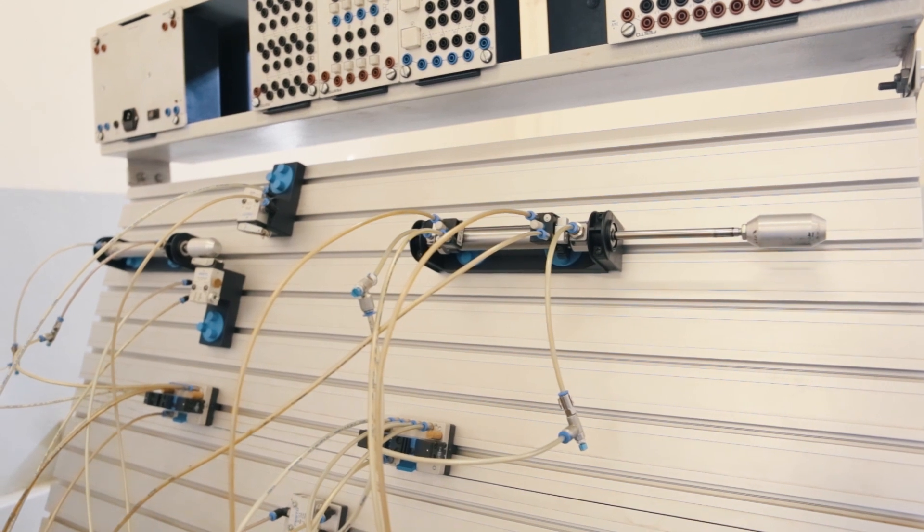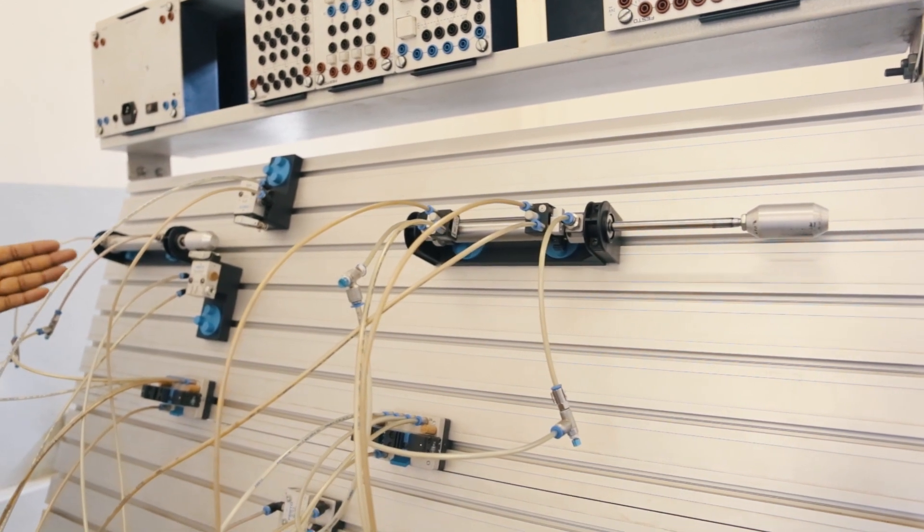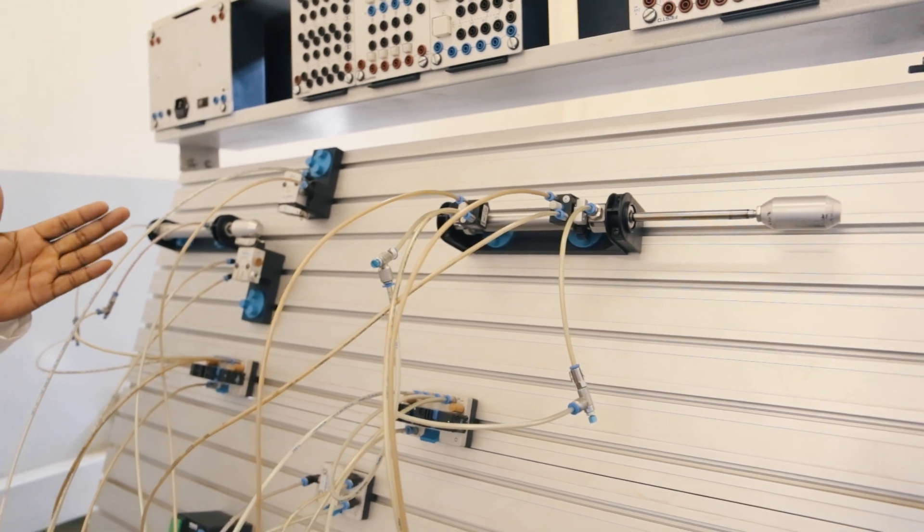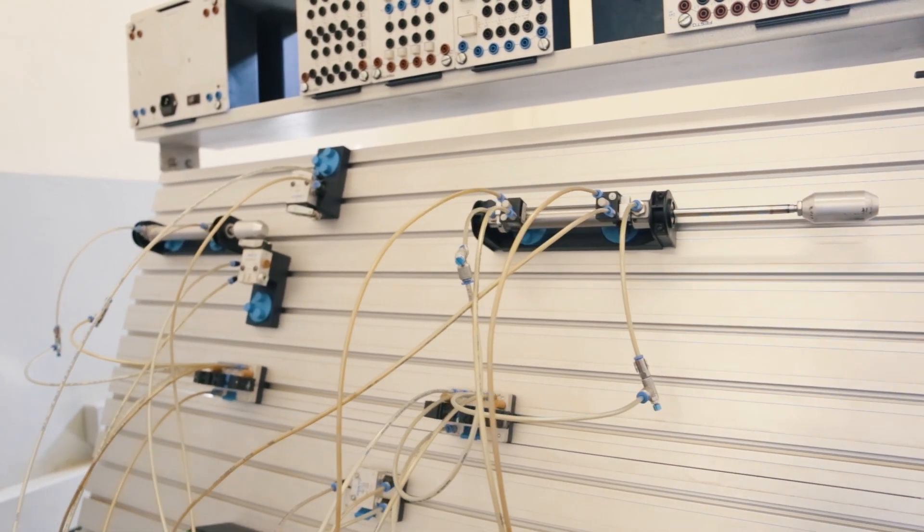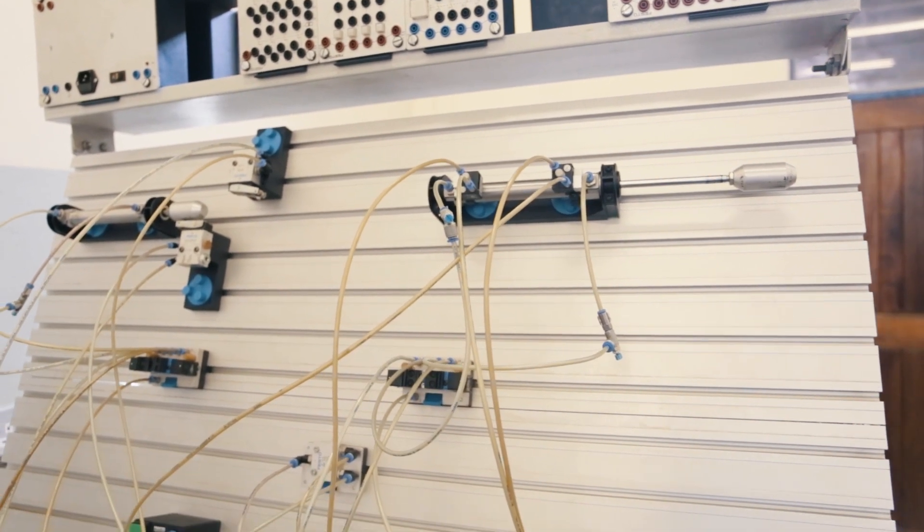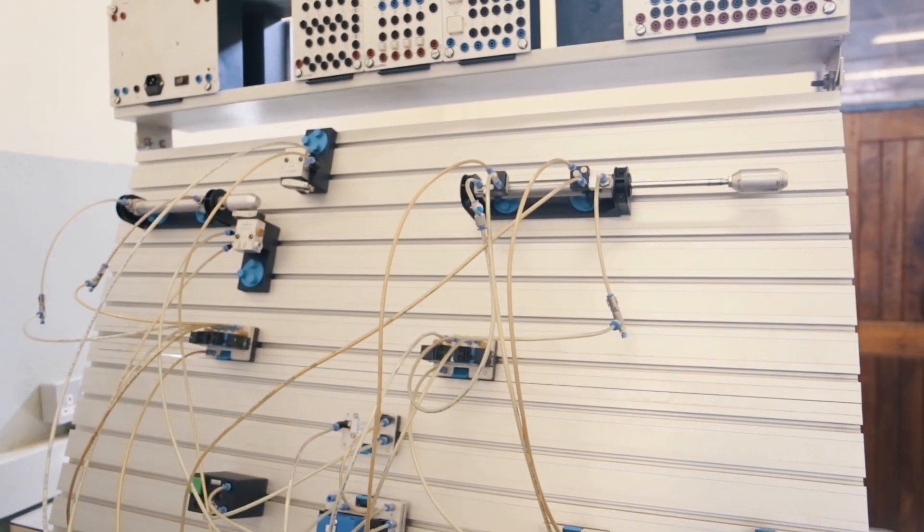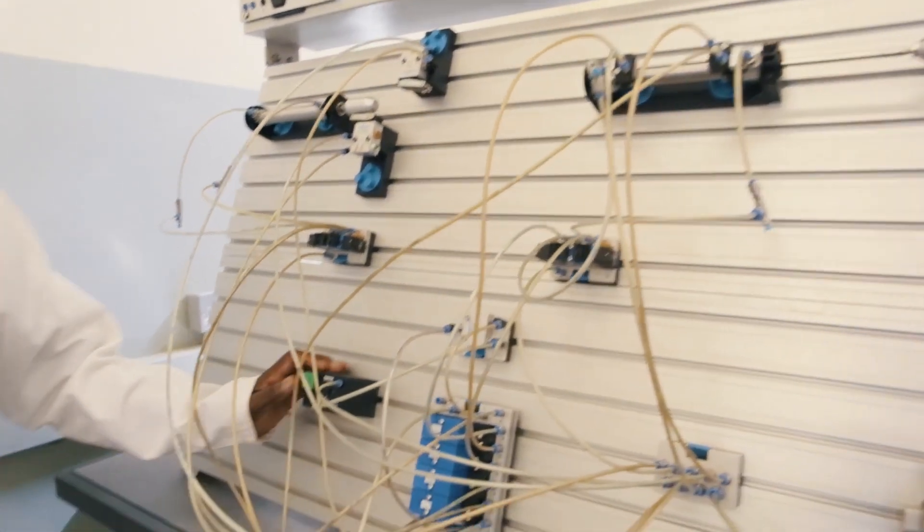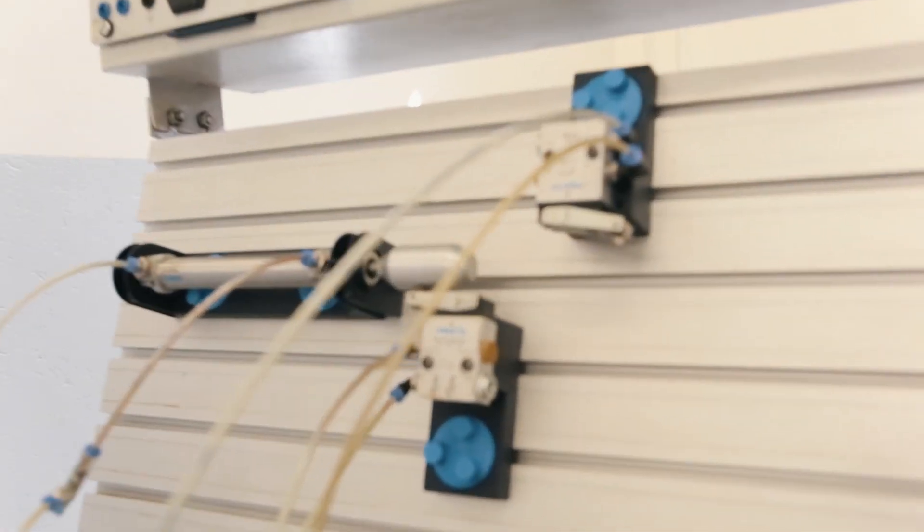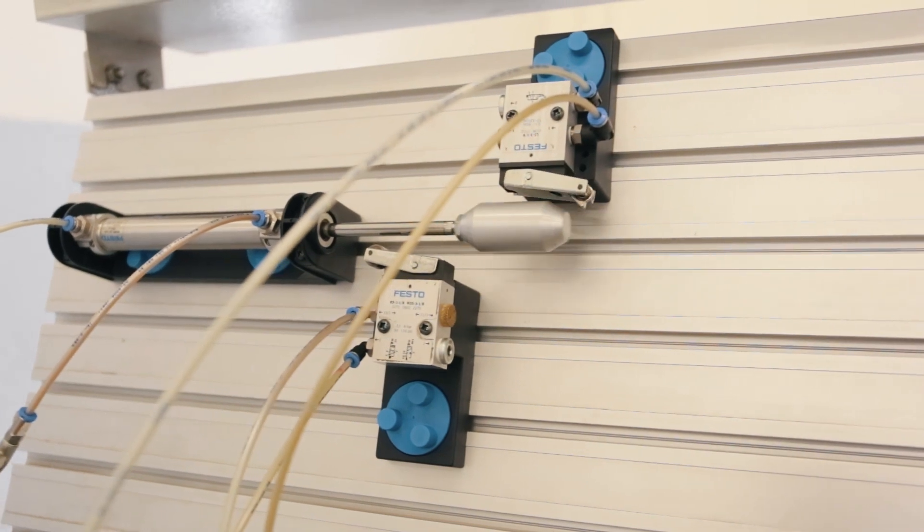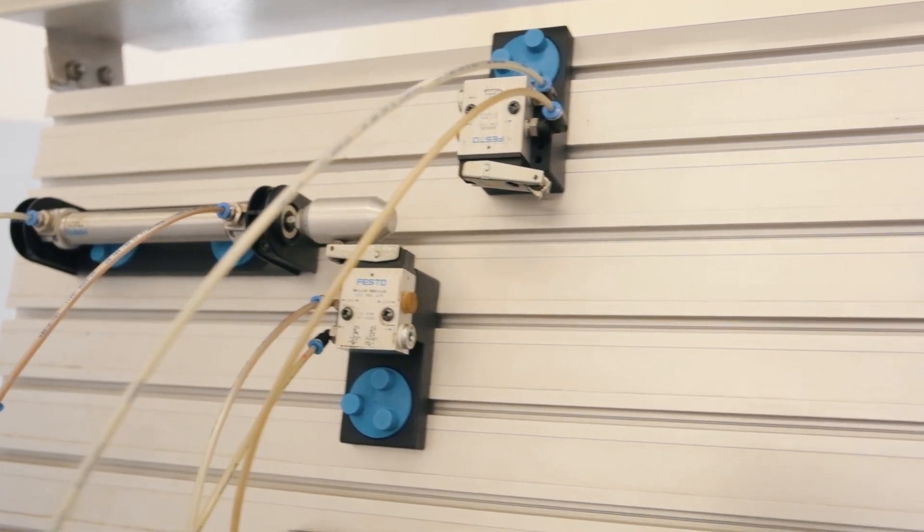What is happening is a sequence because cylinder number one first extends, actuates on the limit switch, then comes back on the other limit switch. That's when cylinder number two goes in. Then after that, the memory will be resetting so that it goes back to its original position.